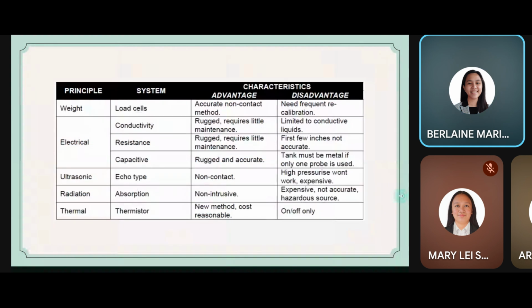Next slide po. Para naman po sa weight is yung load cells, which measure the weight of the liquid, which makes them accurate and non-contact. So the liquid never touches the measuring device. The disadvantage is that they need frequent recalibration because changes in temperature or mechanical stress can affect accuracy. For electrical methods, the conductivity method is rugged and requires little maintenance, which is good for long-term use. Its disadvantage is that it only works for conductive liquids, so it cannot be used for oils or other non-conductive fluids. The resistance method is also rugged and requires little maintenance, making it durable. But the first few inches are not accurate, so it cannot be relied on for small amounts of liquid.